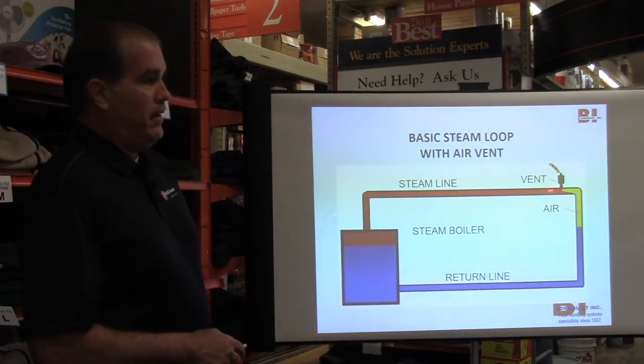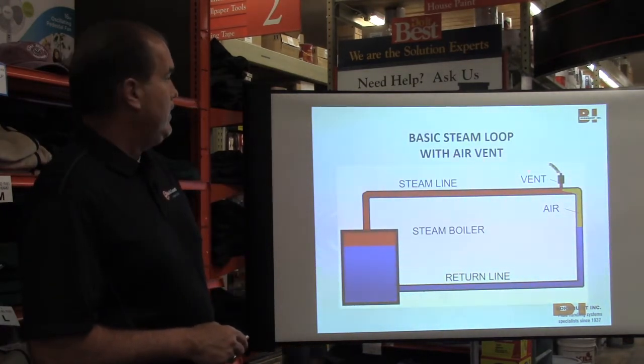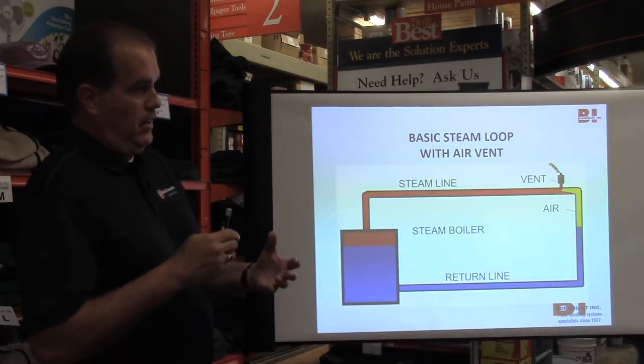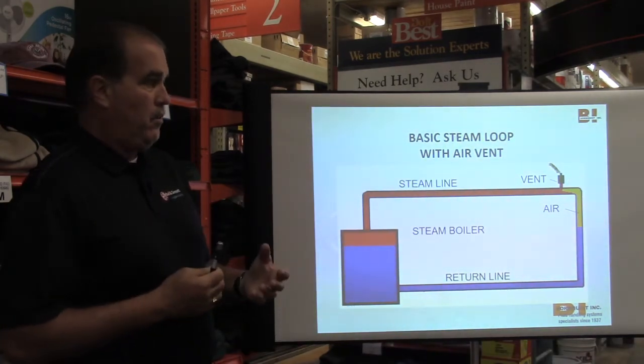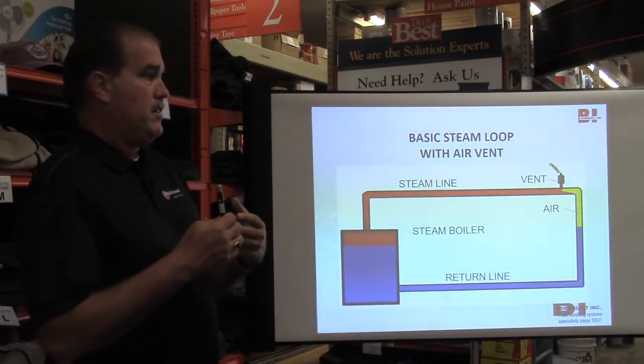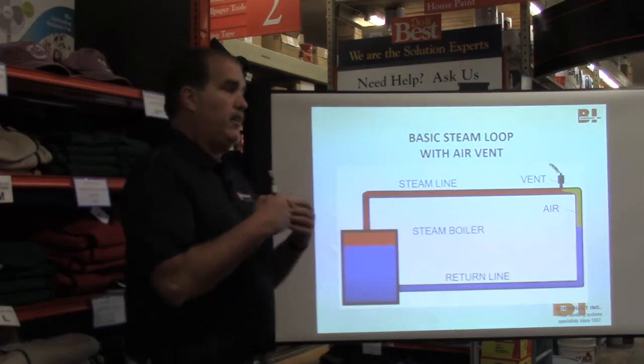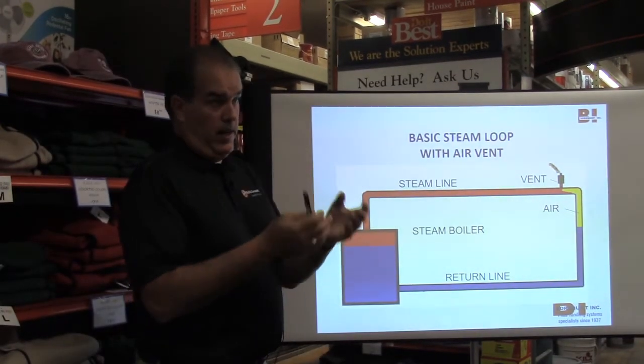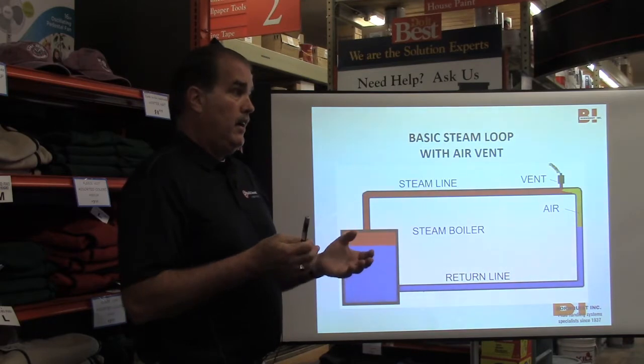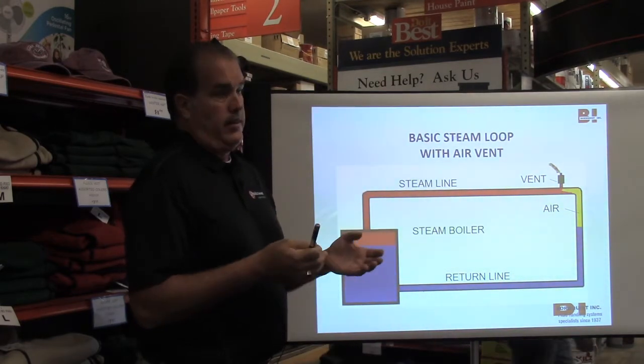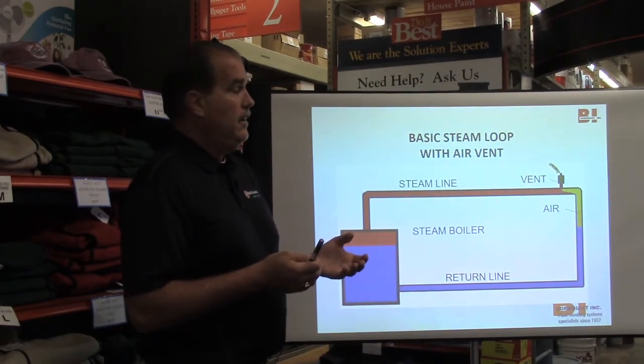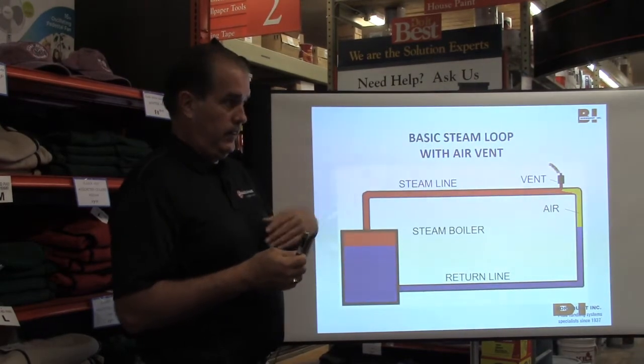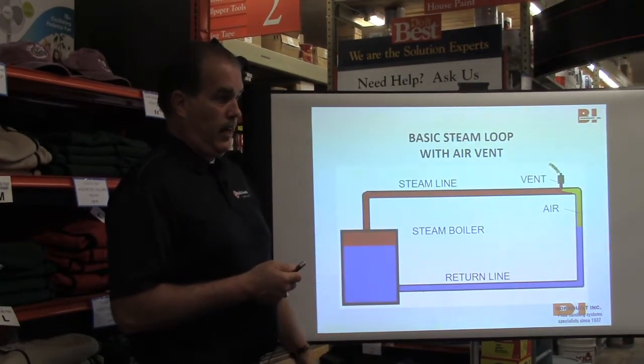Now we're talking vents. We already had some conversation about venting. Steam systems vent cycle a lot more than water systems do. On a water system, if you get a little air slug that goes through, the vent might vent. If you drain it and you're filling it up, it's going to vent. But for the most part, it sits there and does nothing except stay shut. A steam system's constantly cycling. The vent's constantly cycling on and off.